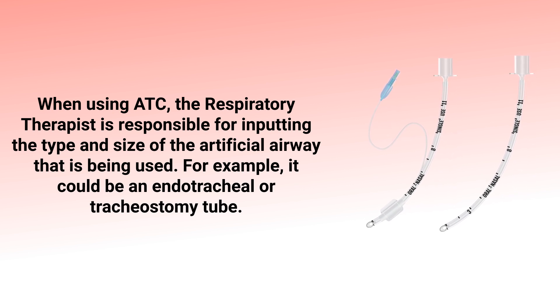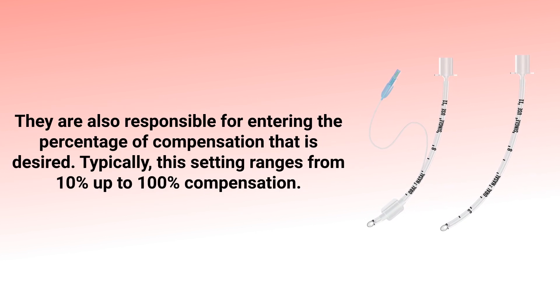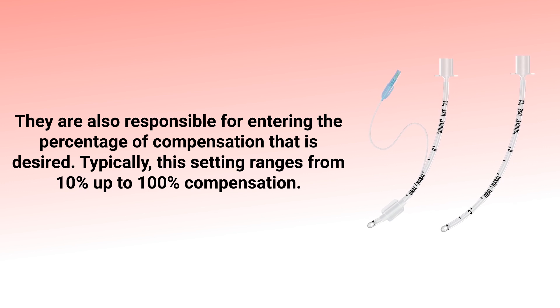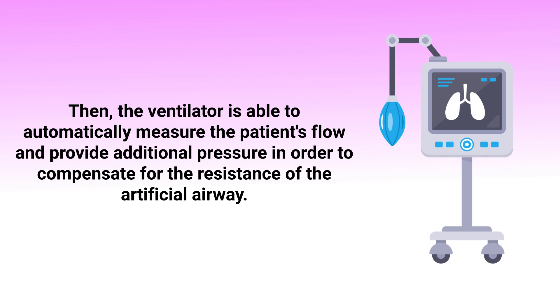When using automatic tube compensation, the respiratory therapist is responsible for inputting the type and size of the artificial airway being used — for example, an endotracheal or a tracheostomy tube. They are also responsible for entering the percentage of compensation desired, which typically ranges from 10 up to 100%. The ventilator is then able to automatically measure the patient's flow and provide additional pressure to compensate for the resistance of the artificial airway.